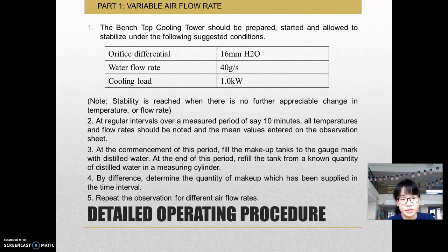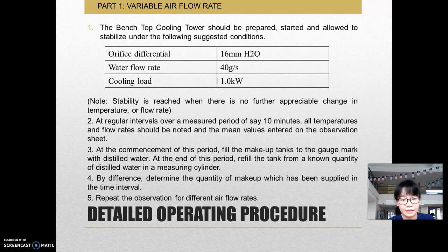Secondly, all the temperatures and readings should be observed at regular intervals over a period of say 10 minutes. Thirdly, at the commencement of this period, fill the make-up can to the gauge mark with distilled water. At the end of this period, fill the can with distilled water using a measuring cylinder. Fourth, by difference, determine the quantity of make-up water which has been supplied in the time interval. And lastly, repeat the observations for different experiments.